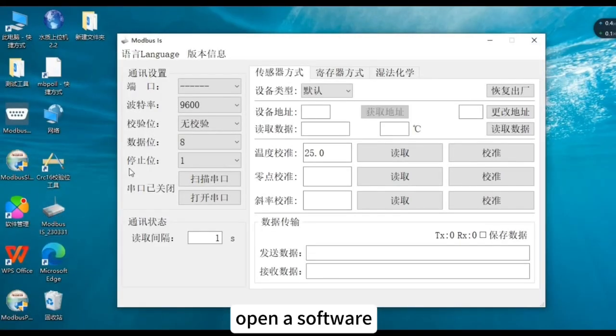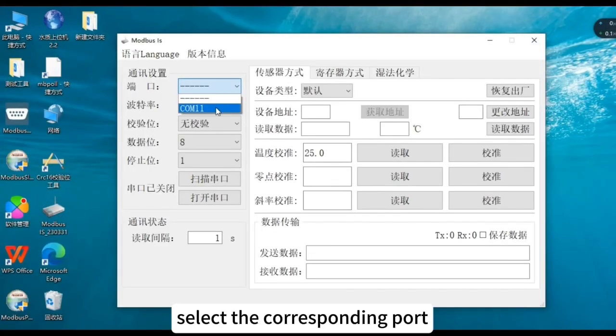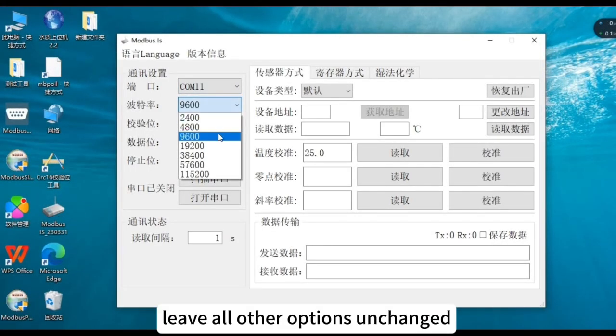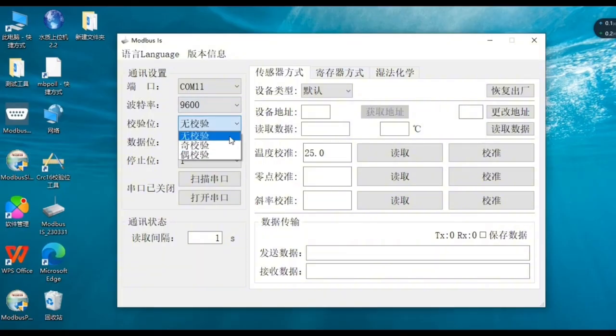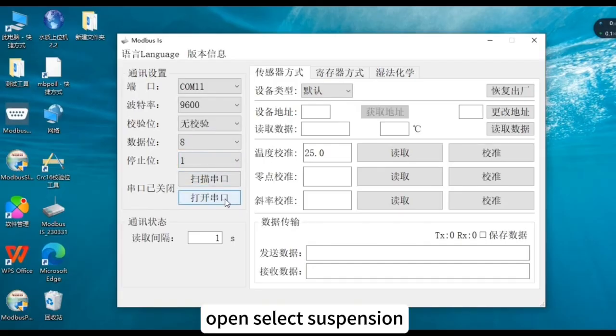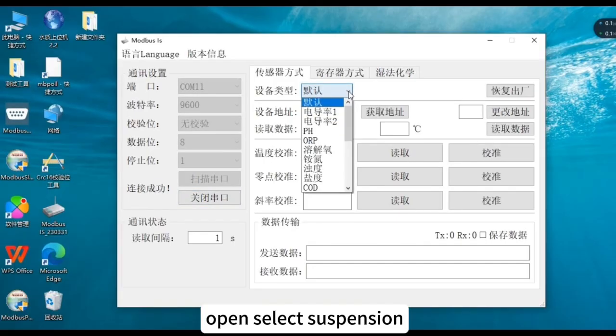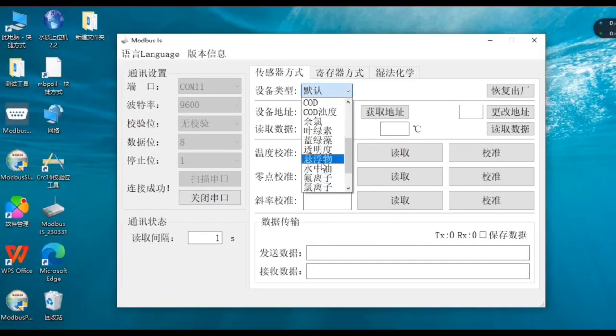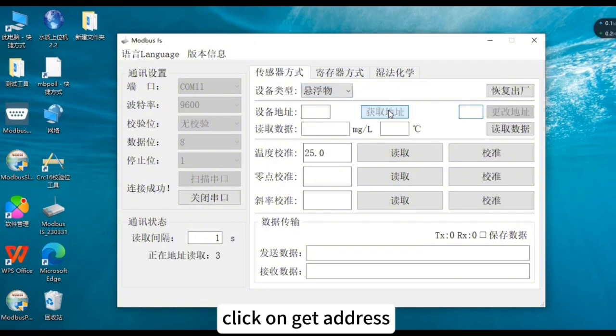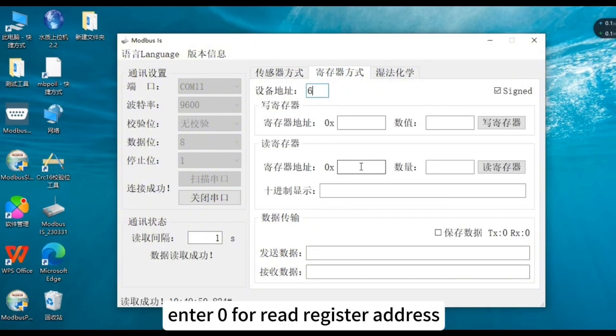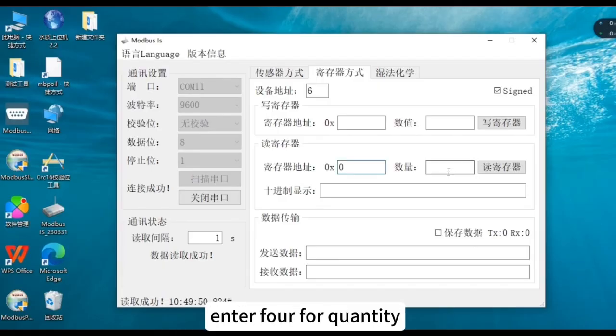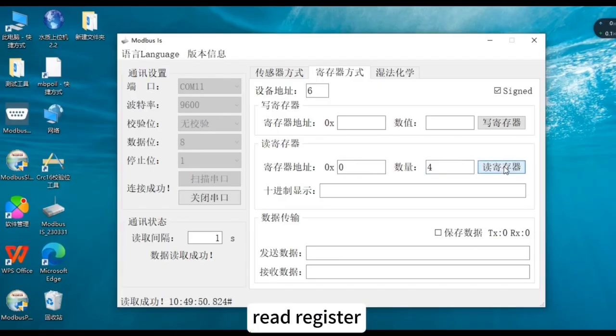Open the software. Select the corresponding port. Leave all other options unchanged. Open. Select suspension. Click on Get Address. Read the data. Tap Register Mode. Enter 0 for Read Register Address. Enter 4 for Quantity. Read Register.